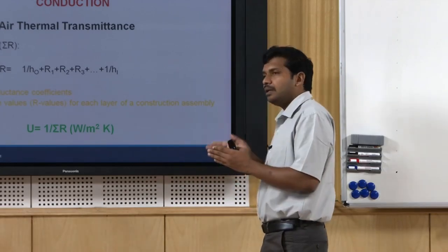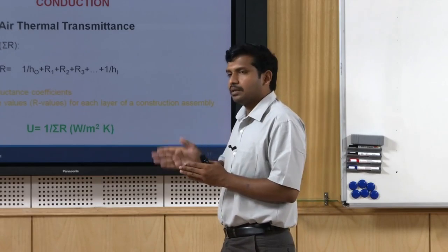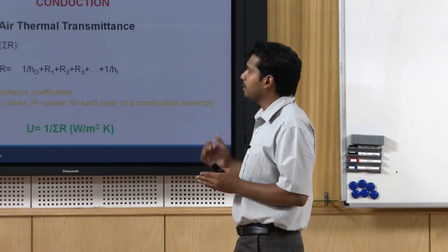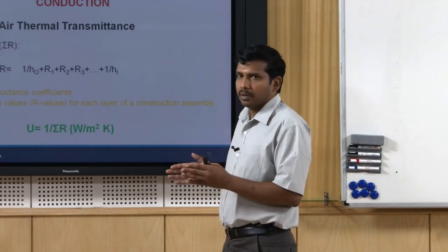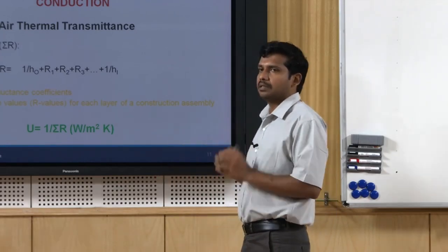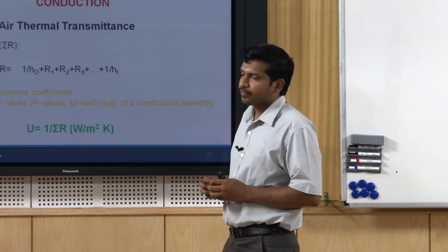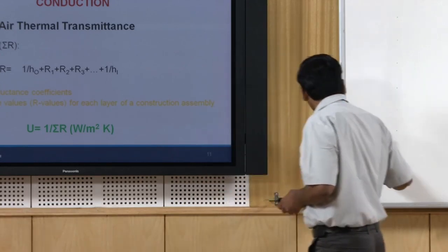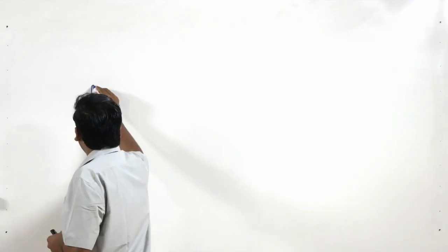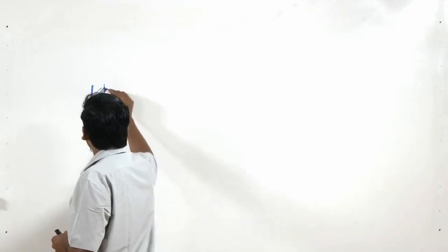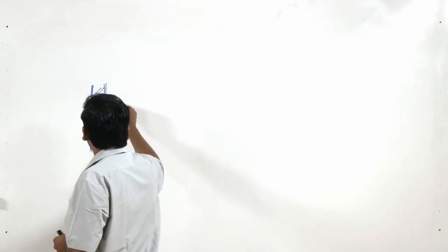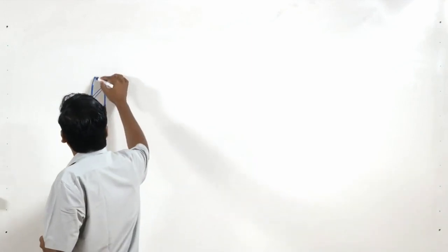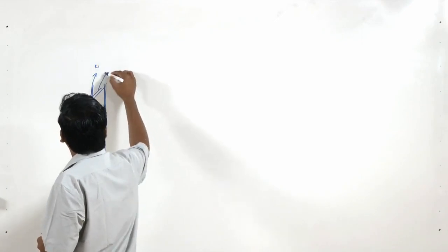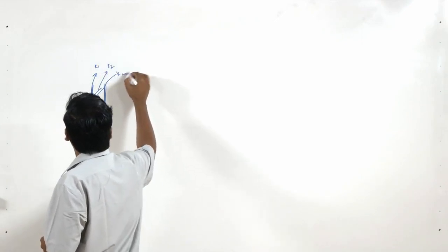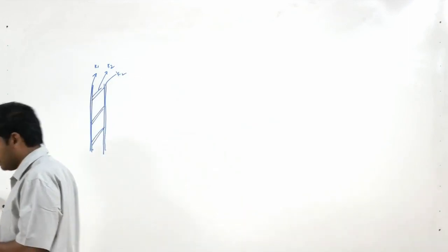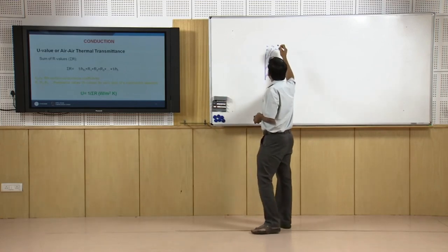If you carefully look at the cross section, what are the cross sectional elements through which heat is going to get transferred? The most common thing, take a brick wall, 210 mm thick brick wall with 10 mm plaster on both sides, totally it makes it 230 mm thick. Now if you draw a cross section, it is going to look like this. You have a layer of plaster, then you have the brick layer, then you have the internal plaster. So there is a conductivity value for this, there is a conductivity value for this, and there is a conductivity value for this. And conversely, you have the thermal resistance.